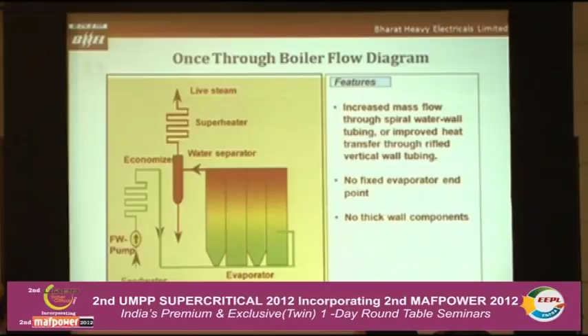So the major differences are the evaporator system, low load circulation and the separator. These are the three major things that differ here. And in the regular drum type boiler, you are aware this is the water wall, this is the economizer, and the superheater. Here you can see the separator. The drum is replaced by a separator, which is a vertical vessel, but it has no internals. It is just a dummy vessel, that's all, like a fractionating column.